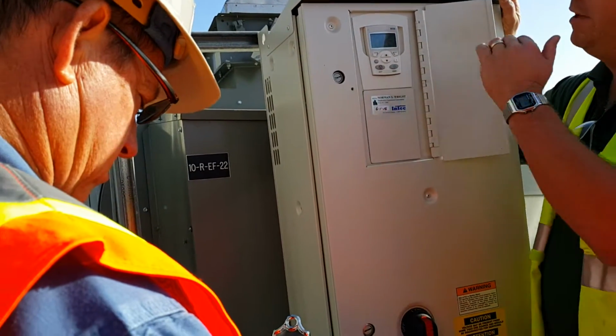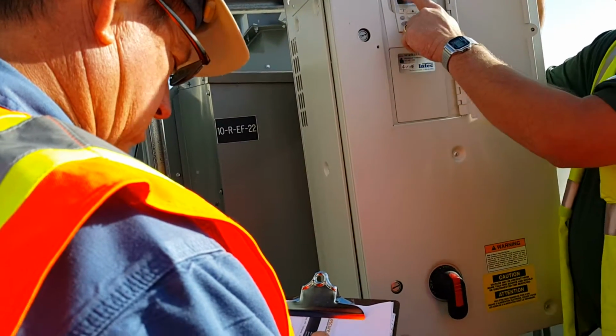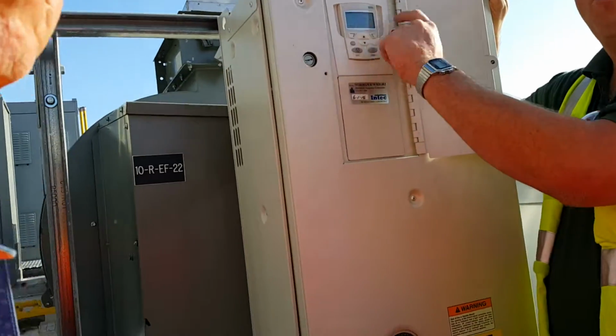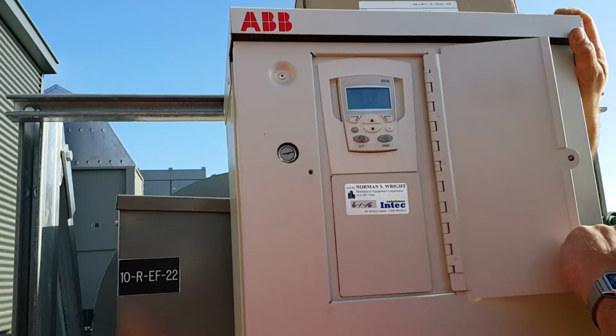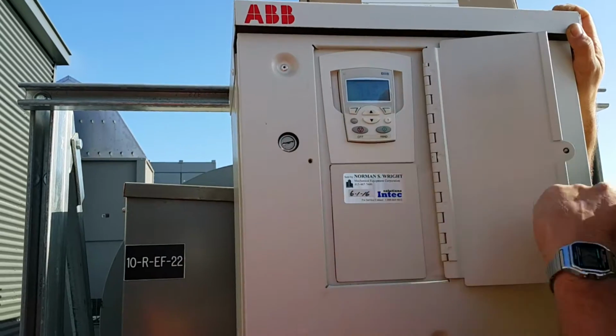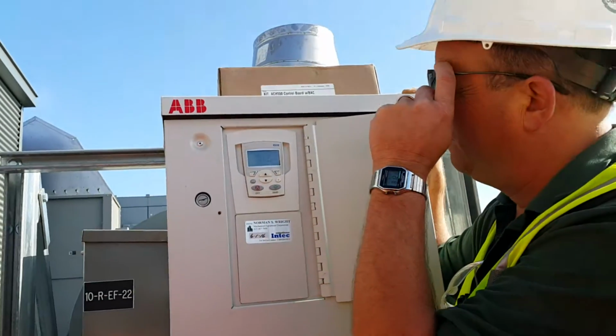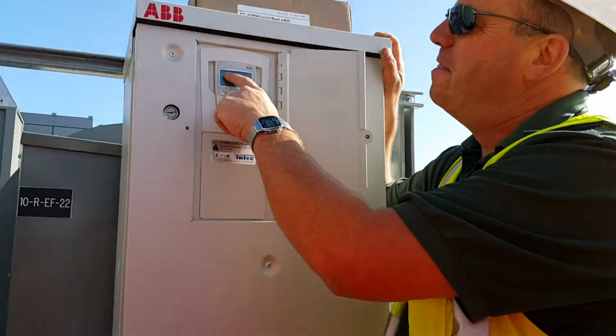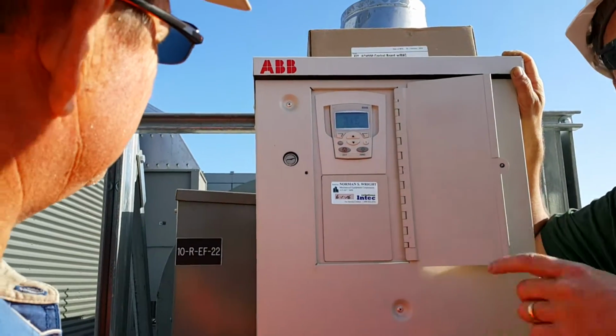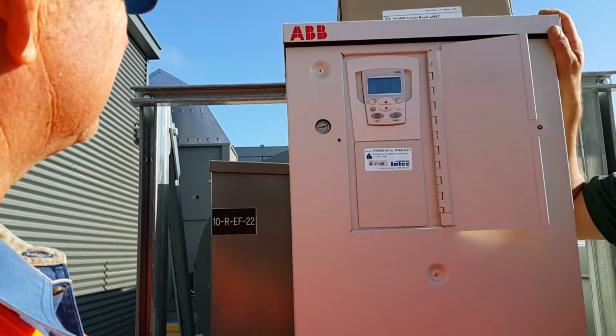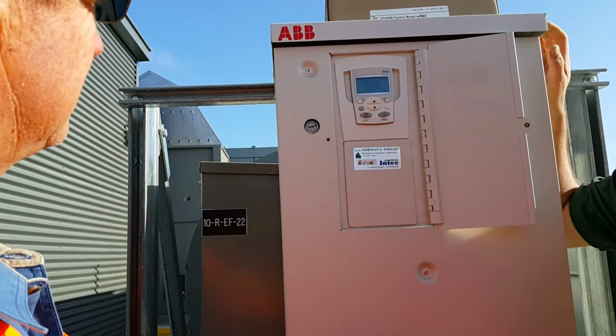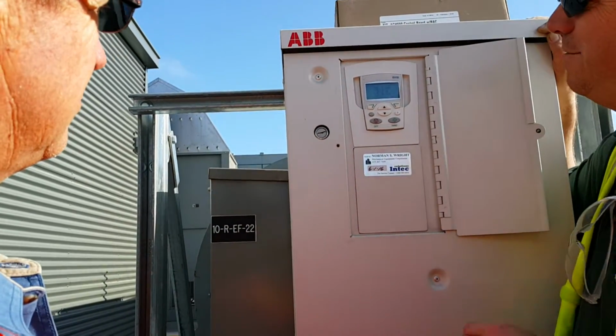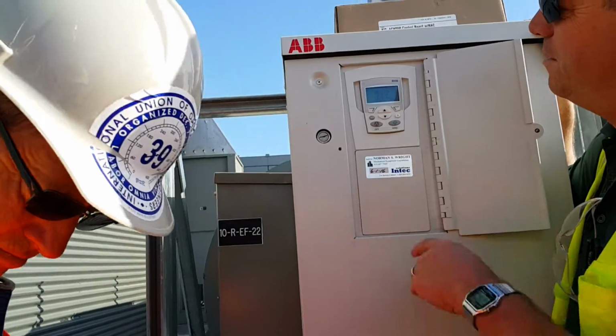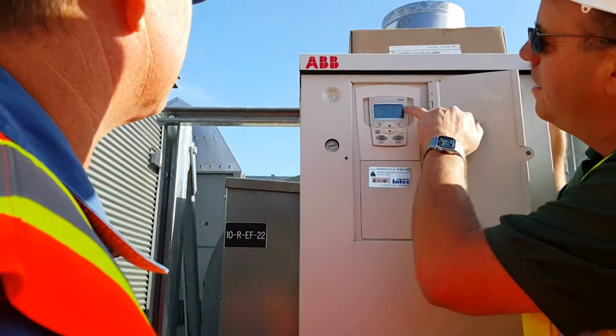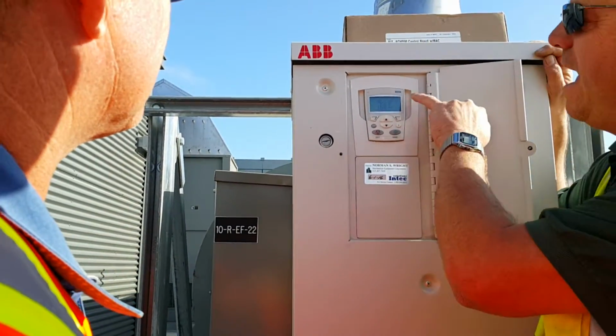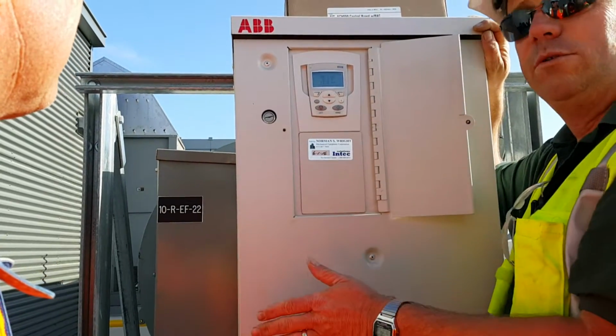A couple things we look at on the display right here, top left-hand corner. We can see whether it's in auto, off, or hand. So right now it should be in auto. There it is. Yeah, it says auto. The next one over, you get that arrow going around in circles. When it's running, it'll spin. So will the motor. But for a remote operation, where the motor's far away, that may be helpful to you. So you can see that it is running. And on the top right-hand corner here, we have what speed the drive is being told to go.